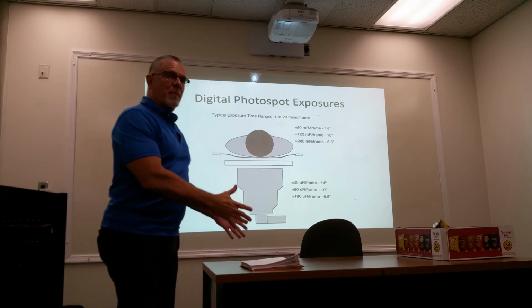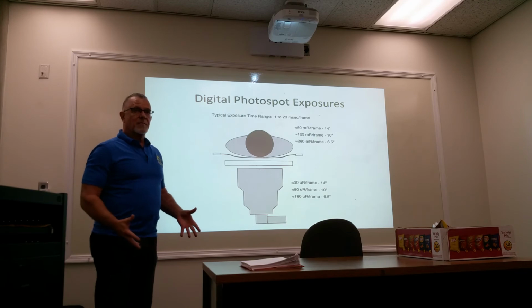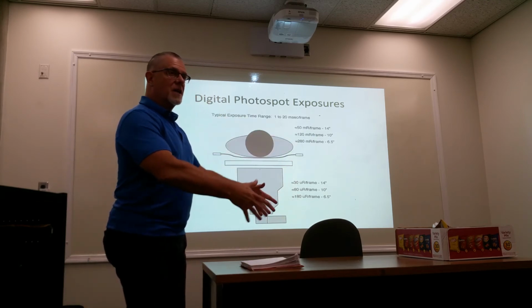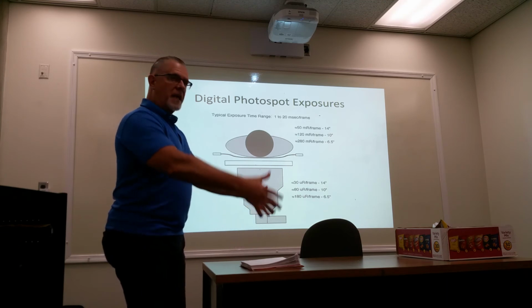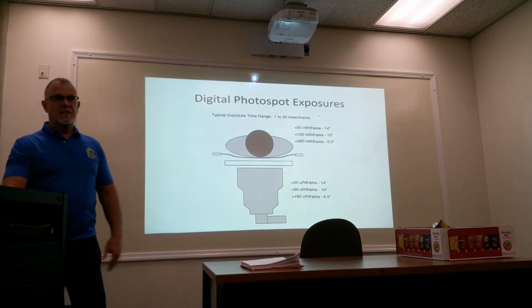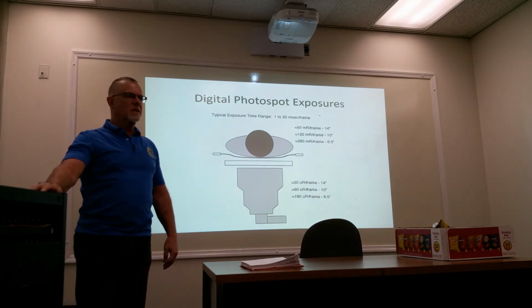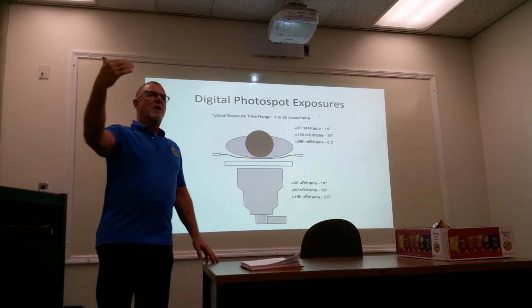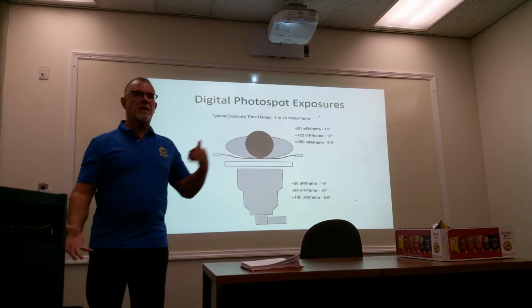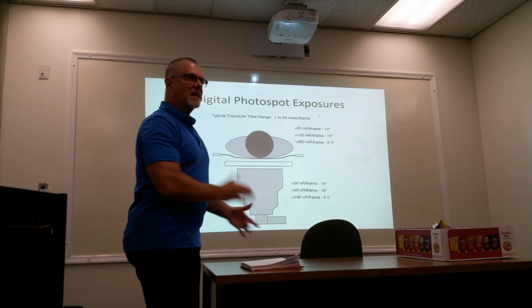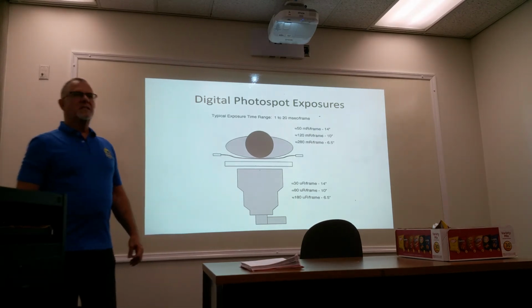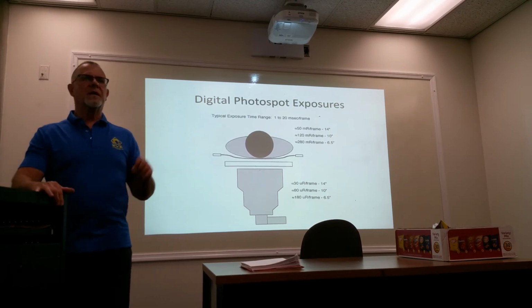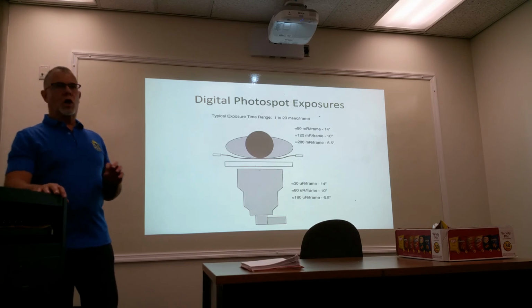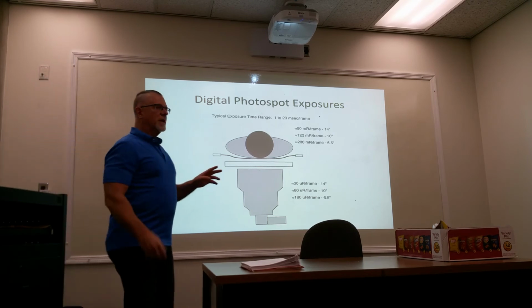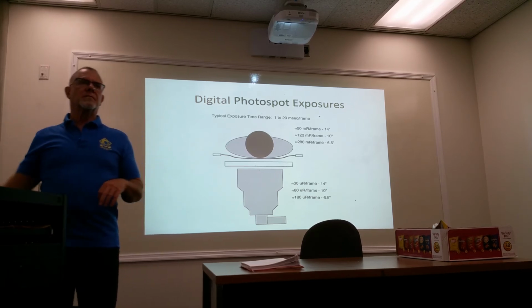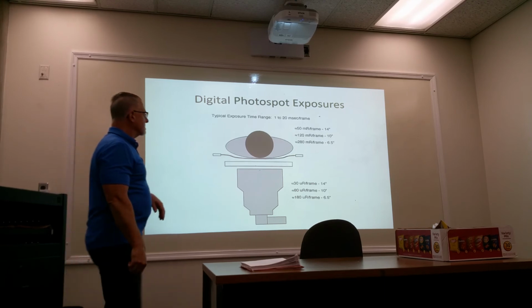But why is that? Because of the imaging. First of all, the law says a couple of things. It's a primary barrier. The law says X-ray has to be confined within the field of view of the image receptor. It can't be bigger than that. And that's tested. Service comes in and does it. Your service engineers from the manufacturer come in and do it. If you have service engineers in your facility, they do it. You probably all have in your facilities a physicist that's connected with them. They come in and test that. And that's the law. So the X-ray beam has to be confined to that. And the second thing is it's a primary barrier. It has to be equivalent to 2.5 millimeters of lead or more. We shield walls for X-ray rooms with 2.5 millimeters of lead, sometimes more. But that's a whole different thing.